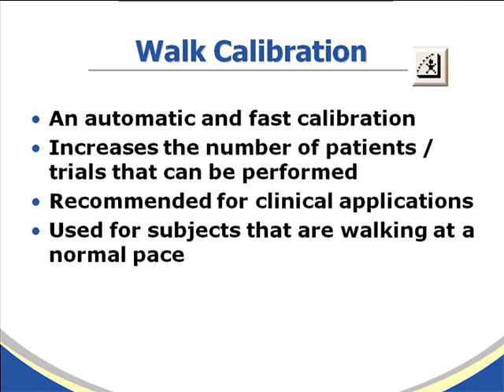Walk calibration is an automated and faster calibration method. There is no need to perform a separate calibration routine because calibration is done automatically with each trial that is collected. It saves time, which increases the number of patients or trials that can be performed. It's recommended for clinical applications where the subject is walking at a normal pace.